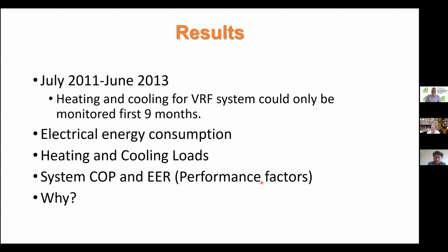So when we started on this project, the building had been operating for, I think, 3.5 years. Some of the data had been lost. There were some gaps in the data, so we picked a period starting with July 2011, where we start to get good data, and we used that. It turned out that in April of 2012, the manufacturer changed the control board of the VRF system. And that changed the flow rates. Since we were using flow hood measurements made during commissioning, we weren't able to recover from that. So the actual comparison covers the first 9 months. But we have good measurements for the ground source heat pump system for the whole 2 years for the heating and cooling provided. So I'll be presenting that.